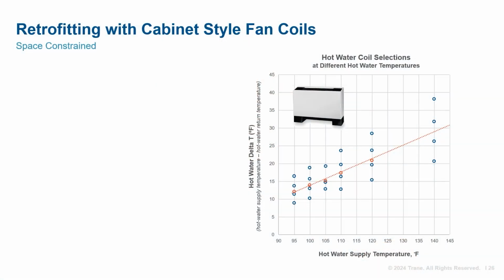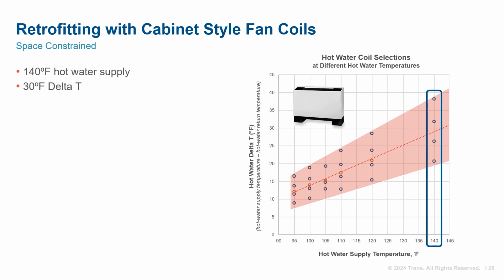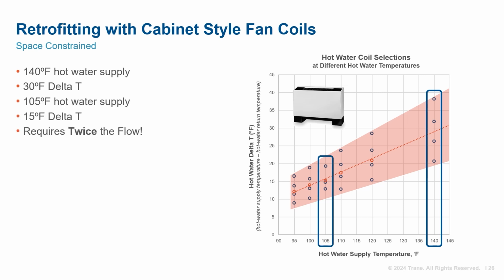So what are the roadblocks that hinder the use of 105-degree hot water? Let's consider a worst-case scenario for forced flow heat exchangers, specifically the retrofitting of a space that has cabinet-style fan coils. Each dot in this chart represents a coil selection at various hot water supply temperatures. On the x-axis is the corresponding fluid temperature drop, delta T, on the y-axis, with the average plotted along the dotted line. This is the expected range of fluid temperature drop when the coil is properly sized for the hot water supply temperature. In this example, the hot water supply is at a temperature of 140 degrees. The delta T of a coil sized for this temperature is approximately 30 degrees. The delta T in a coil sized for 105-degree supply is only 15 degrees.